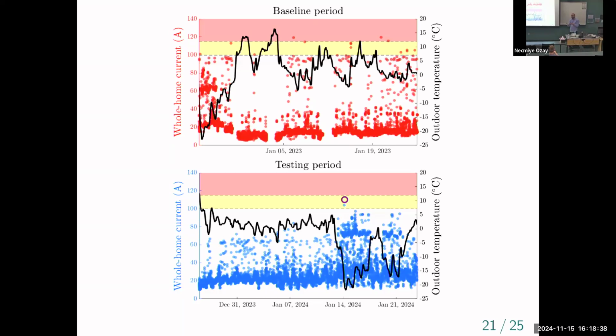It also had a comfort constraint that said if the water temperature in the water heater gets too cold, you must run it. So we got a conflict in our logic: on one hand we wanted to keep whole home current below 100 amps, on the other hand we wanted to keep people comfortable. Our logic said comfort rules, and that's what caused this spike.